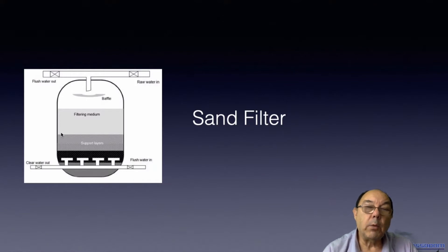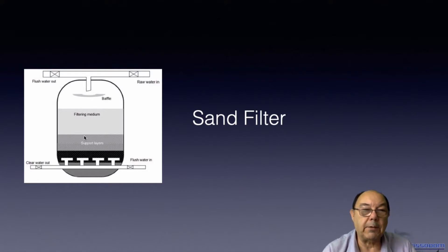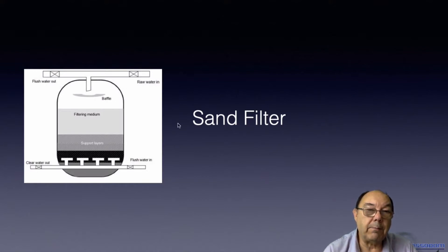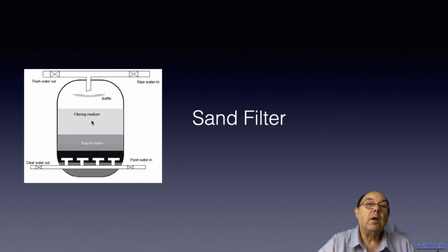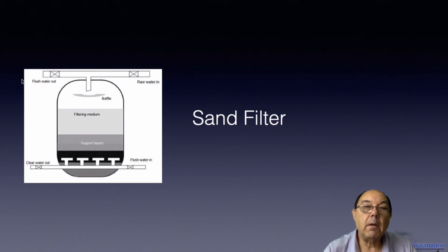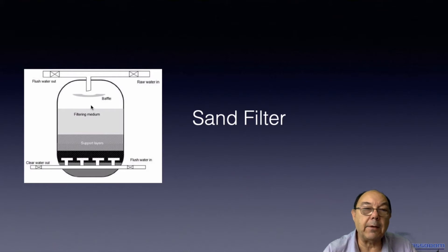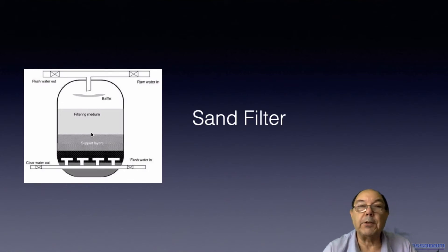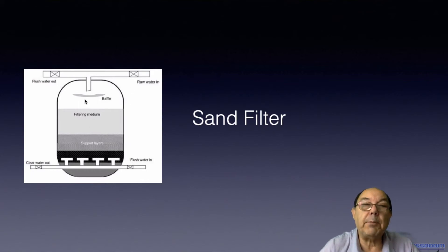At that point the mill will move on to another sand filter — they typically have at least three — and this one will then be back-washed. We close that valve, close this valve, flush water in and up, which churns up all the sand and takes out all the little bits that have been trapped, washing them away. Once the water starts coming through clear we stop the washing process, give time for the sand to settle back again, and by the time that happens the last sand filter in use will just be starting to get blocked — so they'll switch over to this one and carry out the cleaning procedure on the last one.